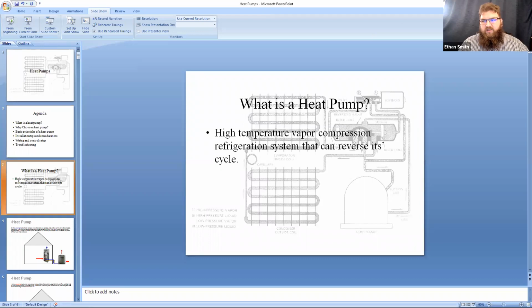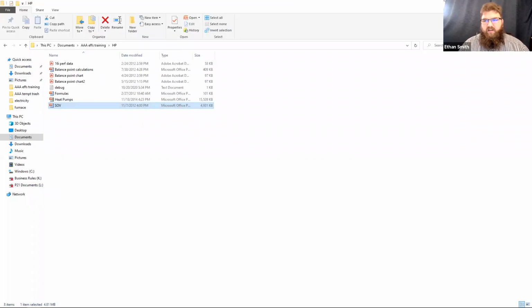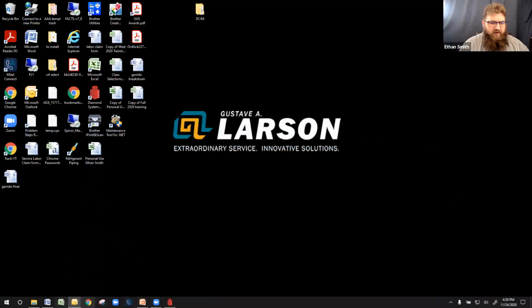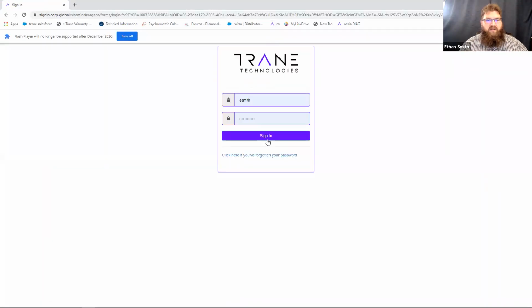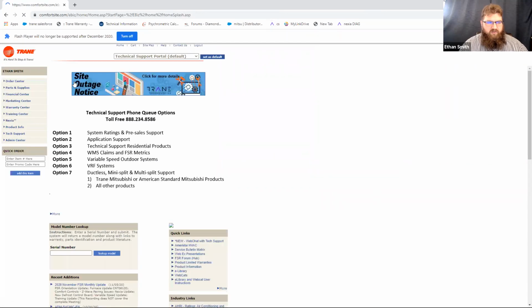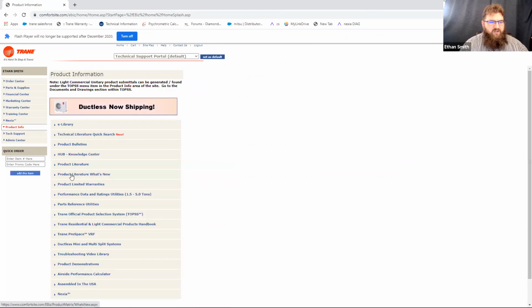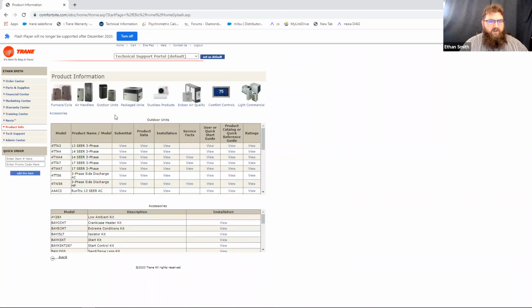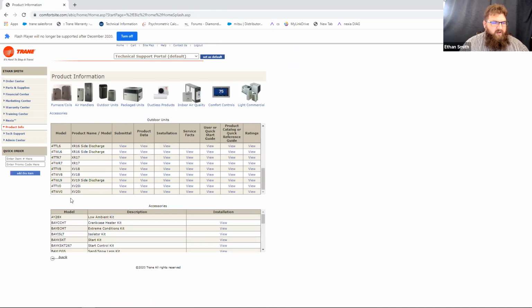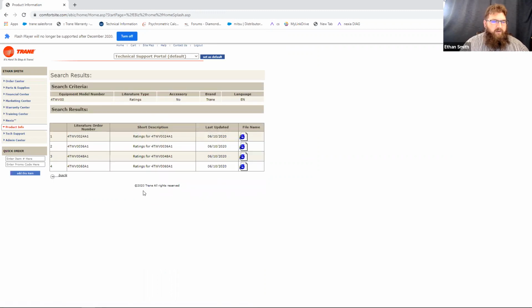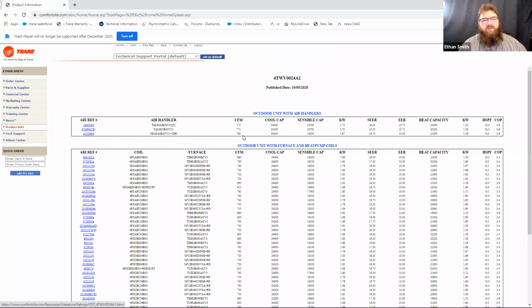So let me show you a little more up-to-date chart. That chart's a little out of date. So if you were doing this for a Trane piece of equipment, I'll show you how to do that. American Standard is the same way. We're simply going to go to MyLink Drive, and all the major manufacturers have websites that will help you with this. I'm going to go into my product information, my product literature, go to my outdoor units, and we're going to pick a heat pump here. So let's just grab a split system. We'll grab one of the variable speed heat pumps, and we've got this column over here that says ratings. The one we were looking at was a 16 SEER. Let's look at a 20 SEER. So there's my 20 SEER 2-ton unit, and we are with a TAM8 air handler. So there's that same system.